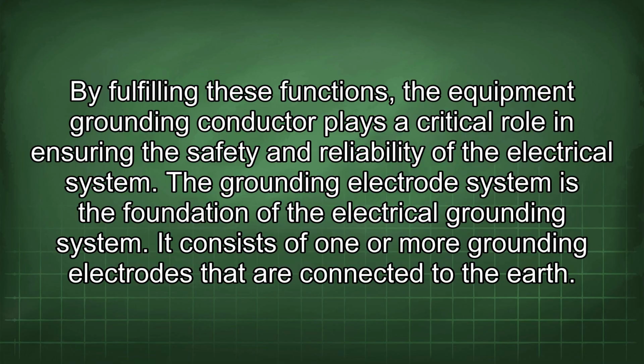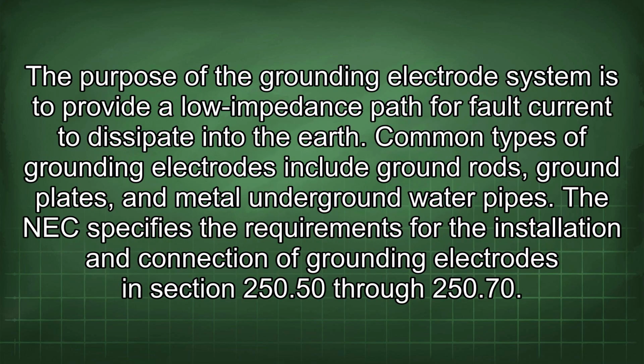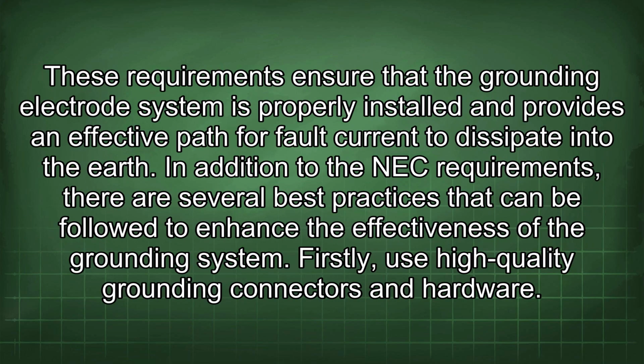The grounding electrode system is the foundation of the electrical grounding system. It consists of one or more grounding electrodes that are connected to the earth. The purpose of the grounding electrode system is to provide a low impedance path for fault current to dissipate into the earth. Common types of grounding electrodes include ground rods, ground plates, and metal underground water pipes. The NEC specifies the requirements for the installation and connection of grounding electrodes in sections 250.50 through 250.70. These requirements ensure that the grounding electrode system is properly installed and provide an effective path for fault current to dissipate into the earth.